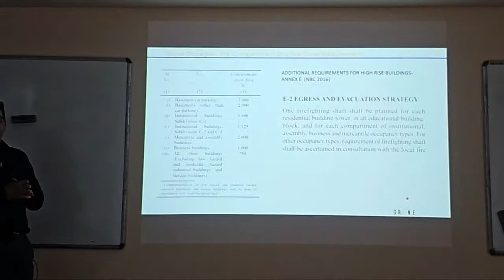Then we talk about the egress and evacuation strategy - how you move out of the building. That speaks about the egress strategy. This is also a requirement from the National Building Code in terms of fire tower arrangement - you have a fire tower and an elevator which allows the firefighter to come in and pull people out, and then they are able to exit into the protected staircase. These are all fire component designs.